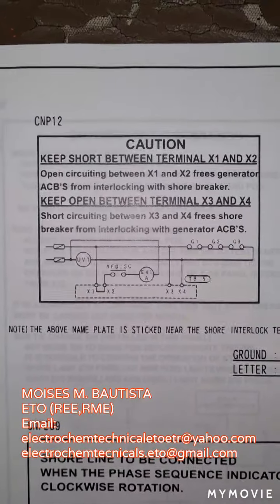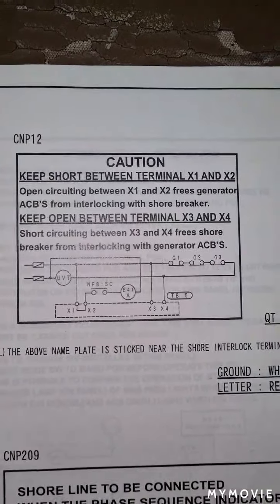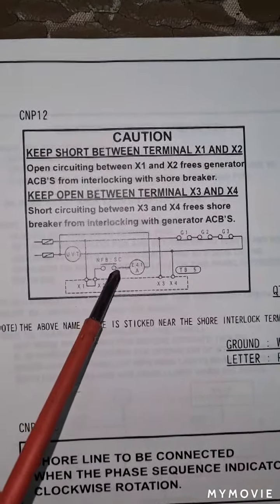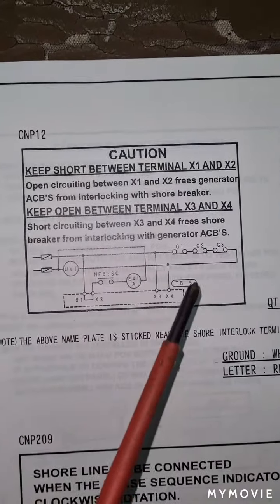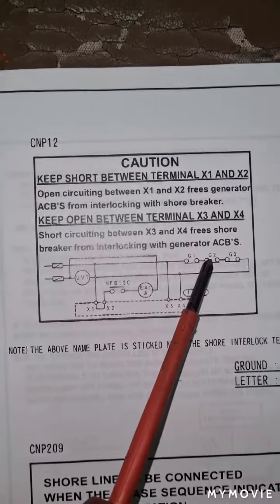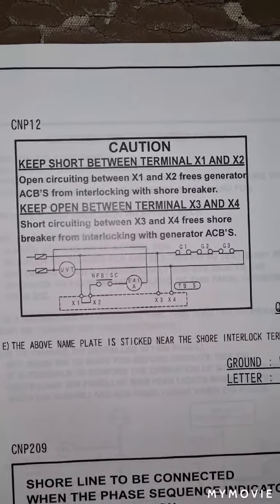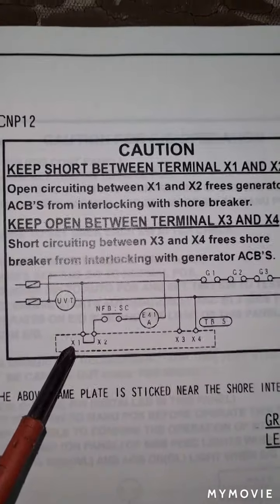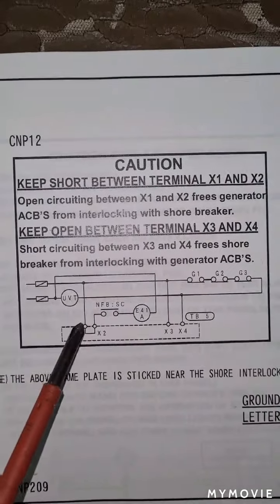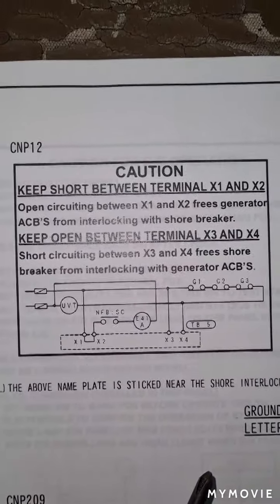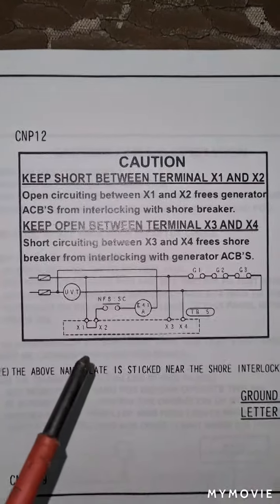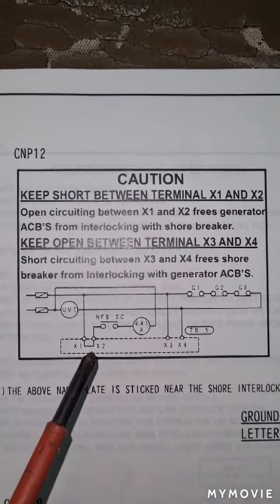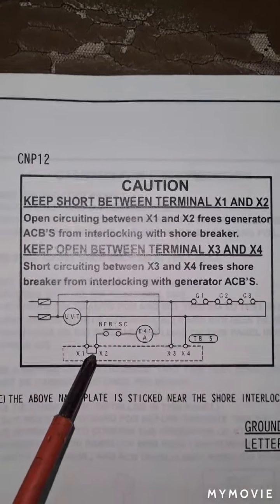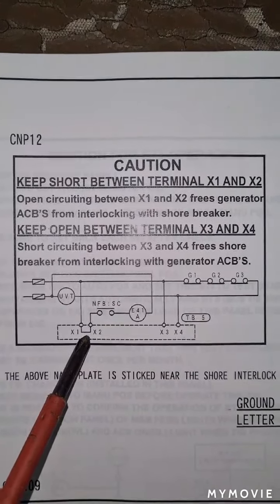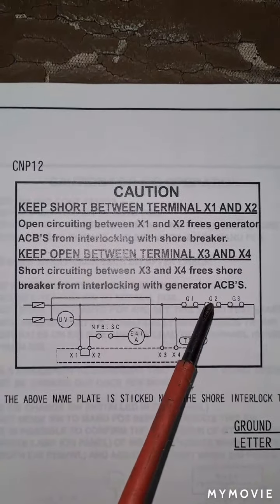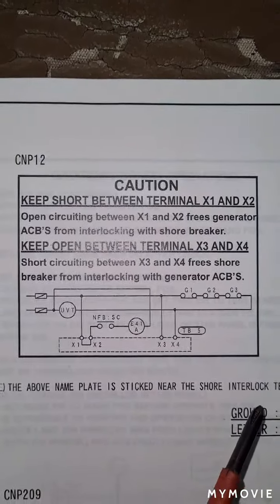Okay guys, what I am showing here is the interlocking system of the shore connection circuit breaker with the generator 1, generator 2, and generator 3 air circuit breakers. From here, you will see there is X1 and X2. These X1 and X2 are the safety interlock. And this safety interlock will not allow you to switch on the shore connection circuit breaker once the G1, G2, G3 air circuit breakers remain on.